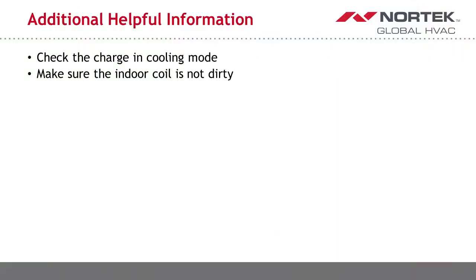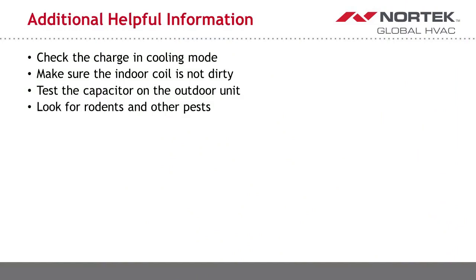So it may be beneficial, especially on air handlers, they're not that hard to get to, to get a look at the bottom side of that coil. Make sure it's clean. Other things I'd be looking at on the outdoor unit: testing the capacitor, make sure it's good. Do a voltage drop across the contacts on your contactor. If you put a voltmeter lead on both sides of the contacts, you should never read more than a 3-volt drop. If you start seeing more than a 3-volt drop, those contacts are pitted, and it's probably about time for a new contactor. Also look for rodents chewing into the wires.